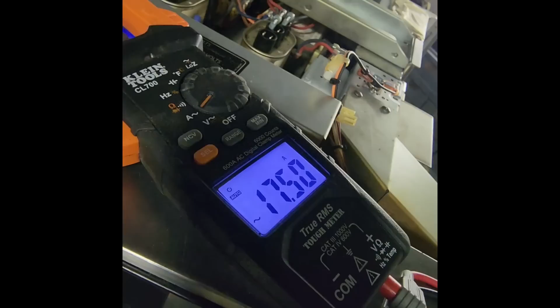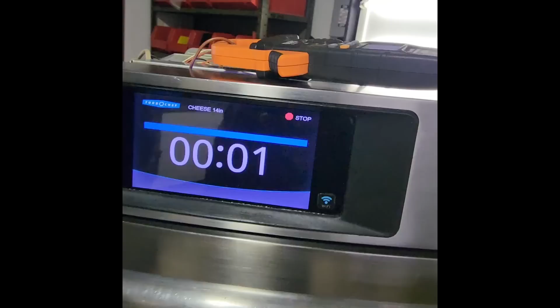Right now this one is cooking fairly nice, and it's looking like it's good to go. I'm just letting it go through its cycle and checking the amp draw while it's cooking. There you can see I got like 17.5 around there, so that's a good amp draw. This is only working off of 208 volts input, so the amperage will be a little bit higher. If I was working off of a 240 line, then I probably would get close to 15 to 16 amps as far as the amp draw goes.